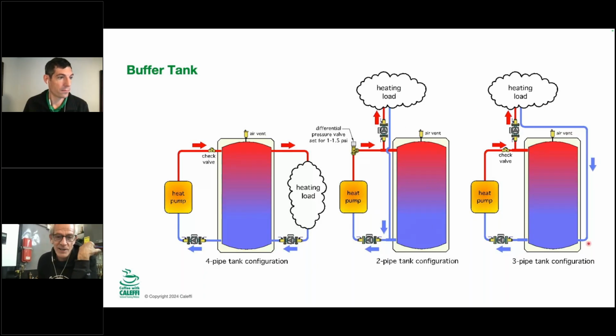So they all have pros and cons. Obviously there's a little bit more piping involved, but what happens on both of these is there's a hydraulic separator right here. So this piece of pipe has to be big enough if we have multiple pumps connected right here, which I do on mine. In my case, this has to be 1.25 inch, 1.5 inch pipe, so that these pumps can run like this, pulling right off of here without affecting flow through the tank. So there are some fine points. If you're going to do a 2 or 3 pipe buffer, you've got to make sure that you have a generously sized pipe.